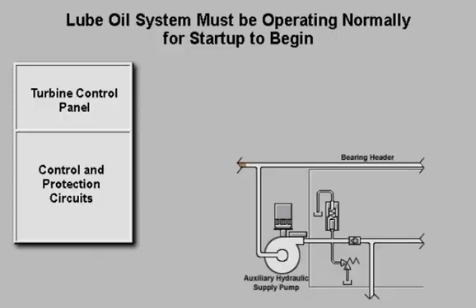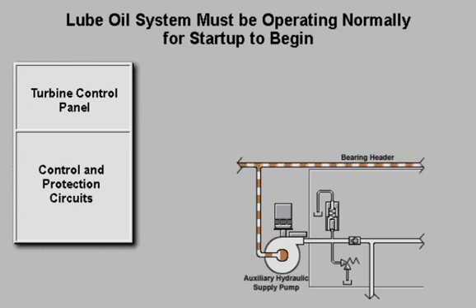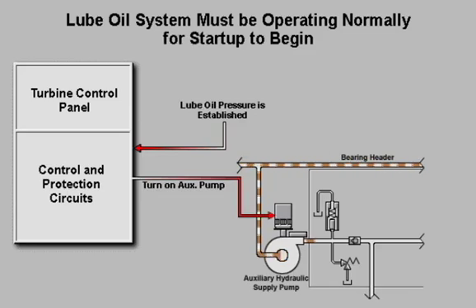During a normal turbine startup, lube oil must be at normal operating pressure before the control system will activate the auxiliary hydraulic supply pump. When the protection system verifies that lube oil pressure is established, the auxiliary hydraulic supply pump turns on and the turbine begins its crank cycle.